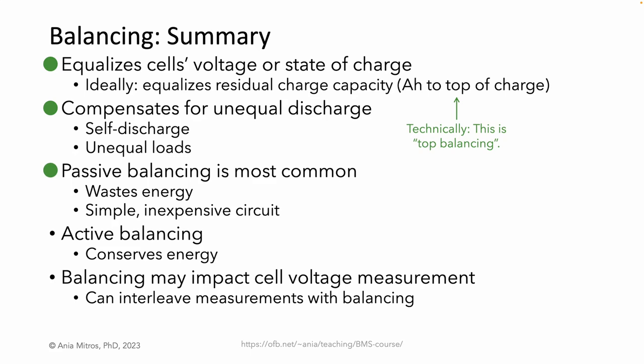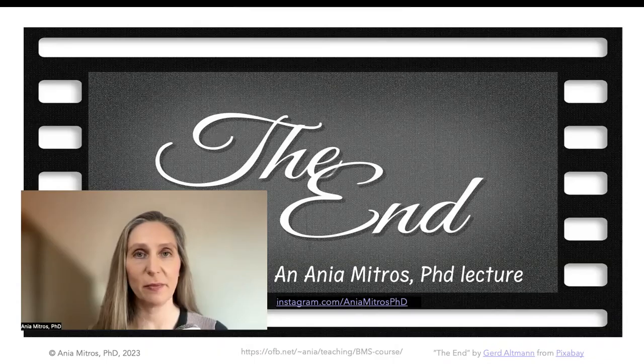Though it wastes energy, most sources of imbalance are orders of magnitude lower than typical application currents. Active balancing conserves energy, but requires more expensive and complex circuitry to implement. Balancing may impact cell voltage measurements to a degree problematic for good state of charge estimation, and we need to design to accommodate that. This completes the lecture on BMS functions in my Battery Management Systems course.